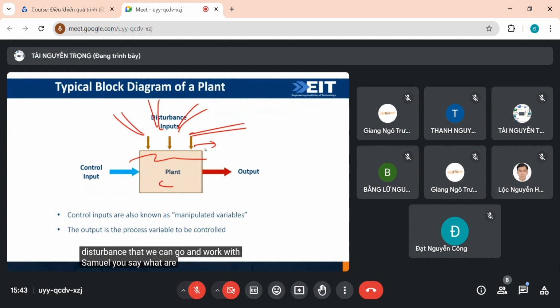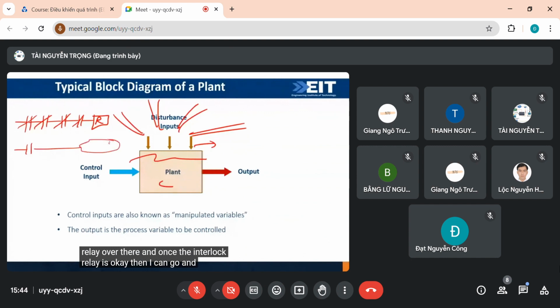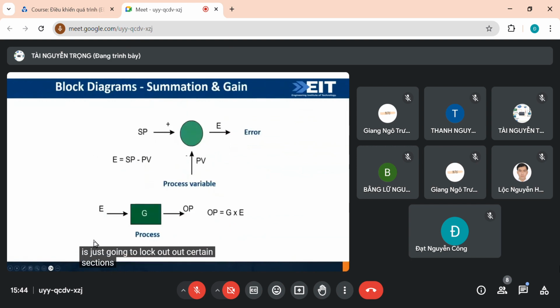Samuel asks, what are interlocks in control? If I have a start-stop process, and my system has no vibrations, is not over temperature, a switch is in the right position, and I have the right air coming in, I bring in my interlock relay. Once the interlock relay is okay, then I can operate the rest of my circuit. So an interlock just locks out certain sections of my plant for me.